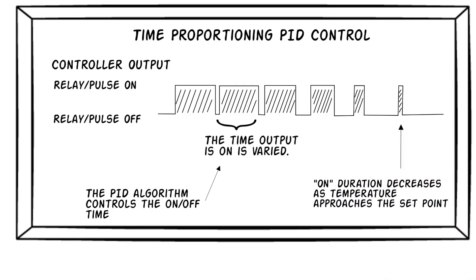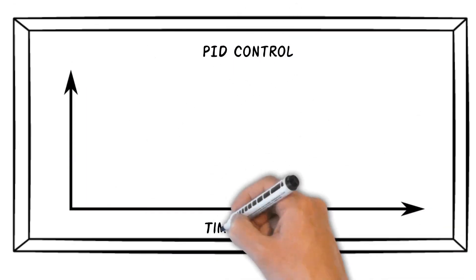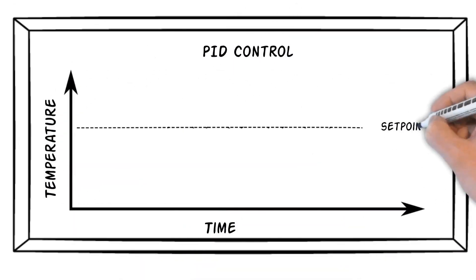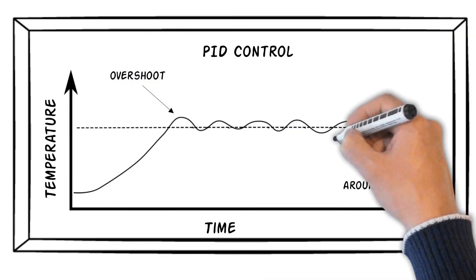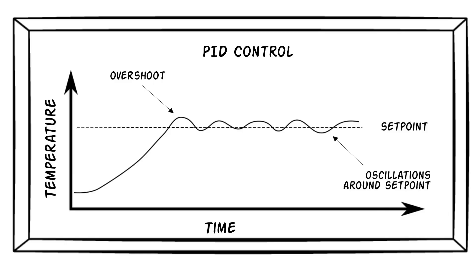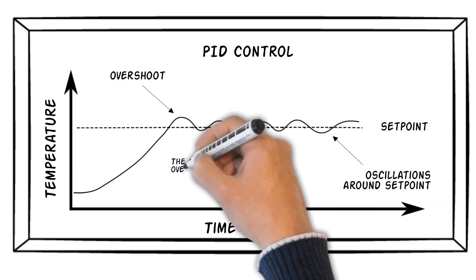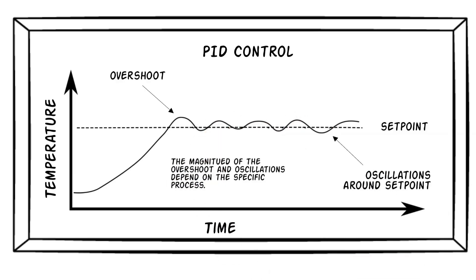This slide shows a typical time-temperature graph of PID control, and as you can see, the overshoot and oscillations are much less than those we saw for on-off control, resulting in much tighter control. The actual magnitude of the overshoot and oscillations depends on specifics of the process, including the thermal mass of what is being heated, as well as the heater size and placement.